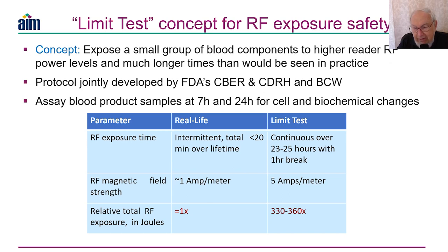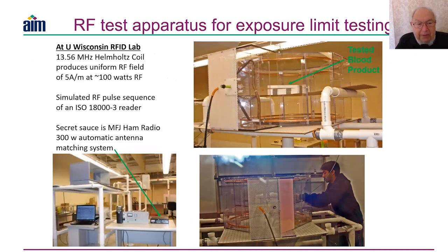Why is that so much? Because we anticipate that a blood bag might have a total interaction with a reader of 20 minutes over its entire lifetime, and we were testing it to 23 to 25 hours. You're likely going to be asked to do this kind of testing for any other biological application using RFID.